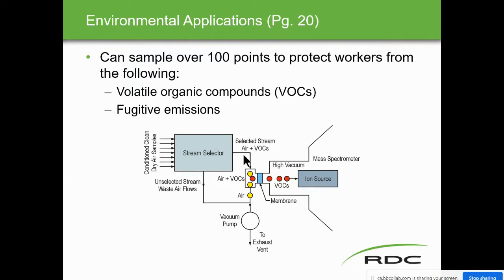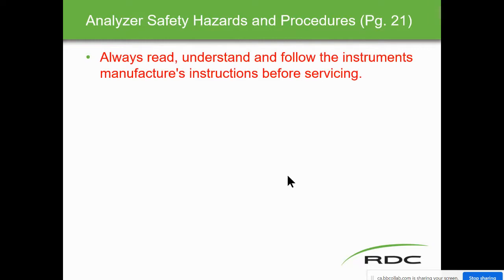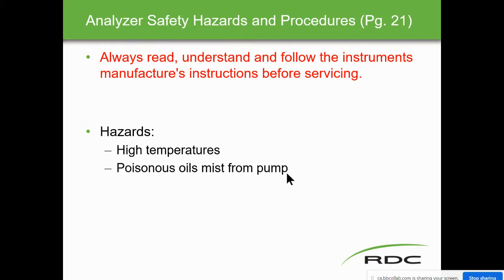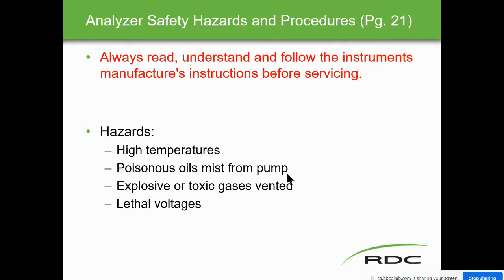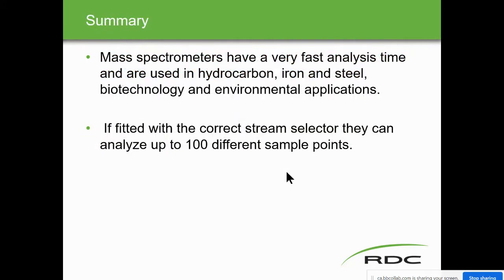Process monitoring applications on page 19: hydrocarbon processing — mass specs often replace chromatographs and are used to measure hydrocarbon and inorganic gases in natural gas, refinery, and petrochemical plants, because mass specs are much faster than chromatographs. Iron and steel production — they measure gases above the molten steel to control quality. Biotechnical — they measure concentration of gases above liquid contained in fermenters and bioreactors. Environmental applications — mass specs can sample up to 100 points and protect workers from volatile organic compounds (VOCs) and fugitive emissions.